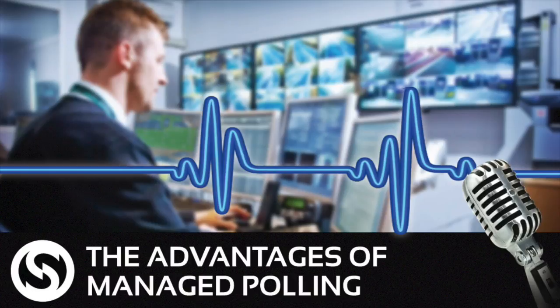We actually send through reasons for dropouts, all sorts of statistical data about that link for that device, including signal strengths. Let's say we've just got a poll. So we've got 1 more hour before we need to notify the control room of potential outage. So what we're doing is saying 10 minutes into that hour, let's send another poll down the communication path. So our system has 50 minutes to recover the connection.